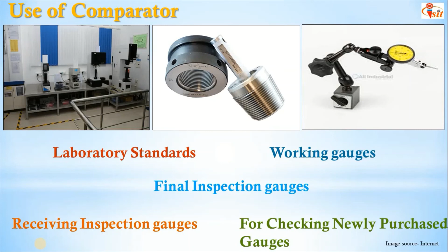So in this session we have seen why we need a comparator, and what the characteristics or requirements of a good comparator are. We use a comparator mostly in mass production, where identical parts are manufactured and where one dimension, like height or width, has to be checked. These height or width dimensions are set by the working standards. Normally we use a slip gauge, so that distance is set by the slip gauge, and based on that we insert the workpiece between the plunger and table gap, and whatever the pointer movement is, if it lies within the tolerance zone, then we accept that part.